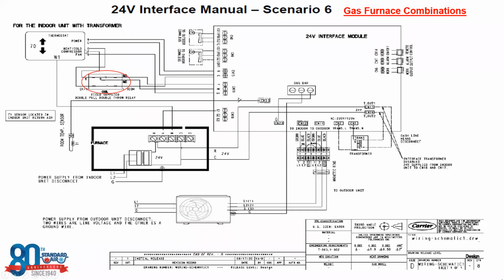Okay, so now we have our Y terminal, which is going to feed out into this relay. And depending on the call, whether we have normally open or normally closed, is going to dictate whether we send that control signal to the Y terminal to turn on the cooling, or normally closed, or we send it to the W terminal to tell the system to turn on for heating. Now you'll see with this single pole double throw relay on there, this is essentially how we're going to be able to differentiate between a cooling call and a heating call for the heat pump.